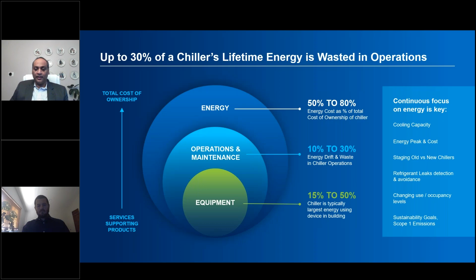In addition to managing chillers manually, we also have the ability to manage them with a machine in the middle—this is where the high performance software comes into play. We have a product called Central Utility Plant that communicates not just with chillers but all major devices in a central plant, including generation resources and boilers. Anytime we have cooling, we also have simultaneous heating and cooling as part of HVAC system design, and optimizing that in real time is critical to getting the most out of facilities and reducing operating costs.